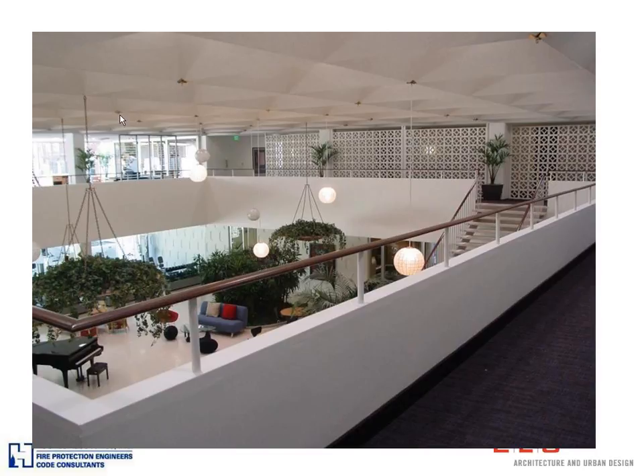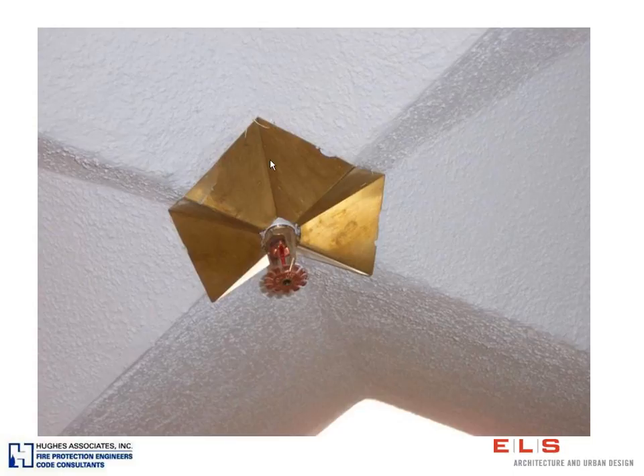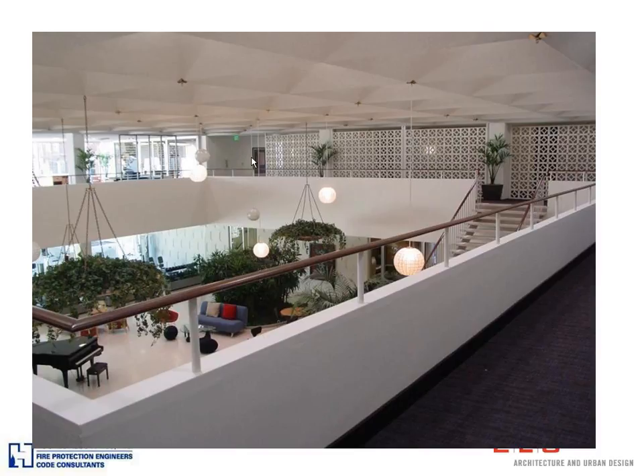And we also did computer modeling to indicate that these sprinklers can be effective by doing a smoke filling model to show that smoke that fills up in the space before it banks down to the sprinkler would not cause a significant delay. And so it's hard to tell from this photo exactly what those sprinklers look like. So what we did is we created a custom designed escutcheon that fits appropriately within the design of the ceiling. And here in this close-up view, obviously you could see a little bit of paint, but as soon as you're far enough away, you don't see anything from the floor. It just looks like it all fits in beautifully with the character-defining features of the building.